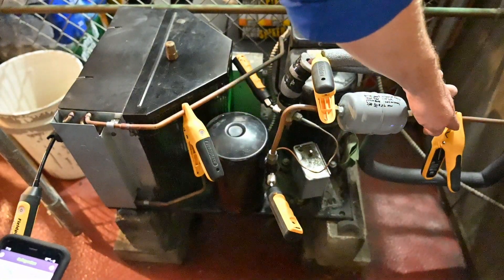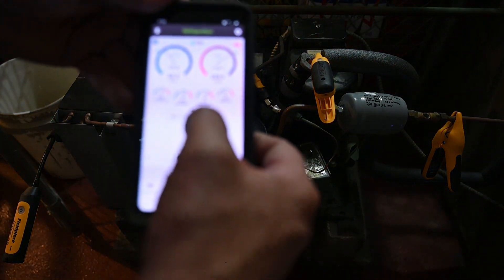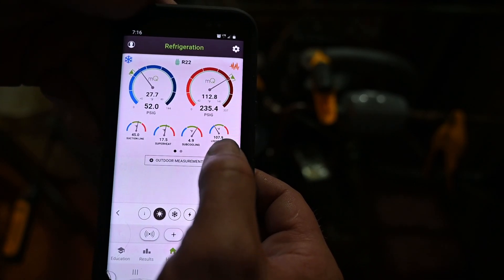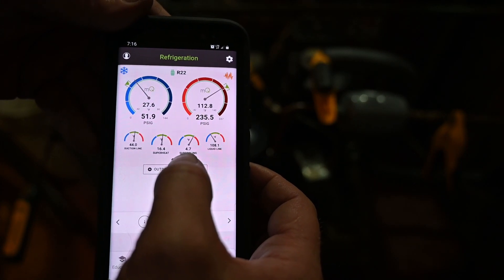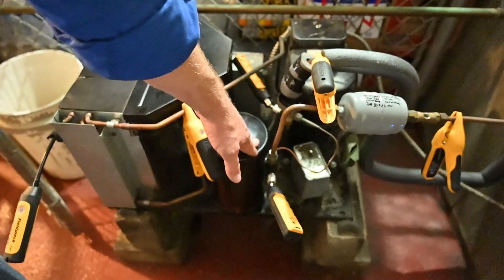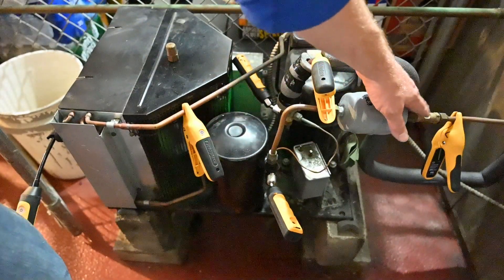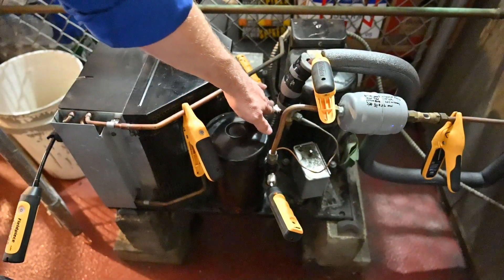We have our actual liquid line temperature with a clamp. My liquid line temperature is at 107.9 degrees, which is good. The app is also calculating our sub-cooling, which is showing 4.9. I'm not worried about sub-cooling at all because I have a liquid receiver. We just need to make sure the receiver is not overfull — all we really need is a solid amount of liquid, which we can confirm through the sight glass.